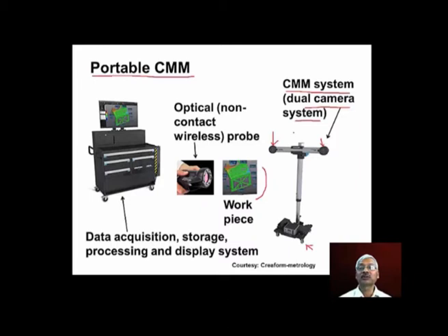The dual camera system will be monitoring the workpiece as well as the probe movement, and it establishes dynamic referencing using the optical triangulation technique.